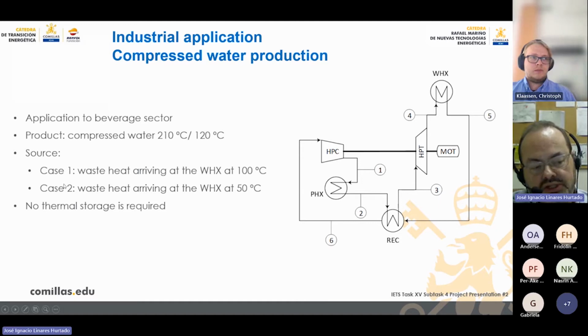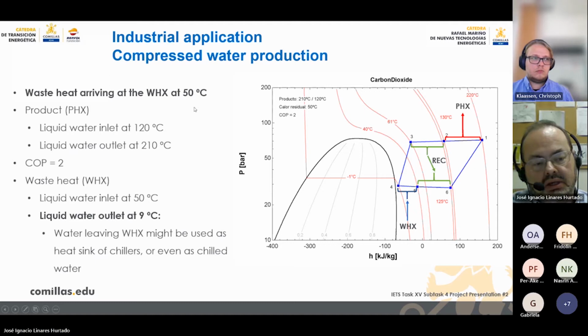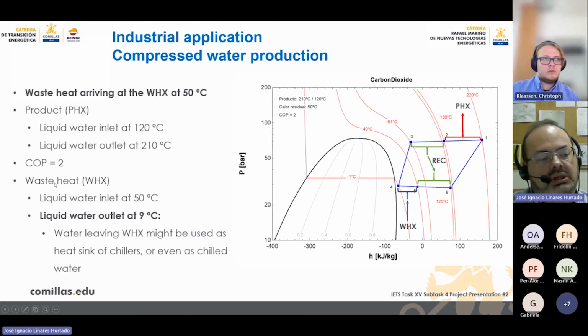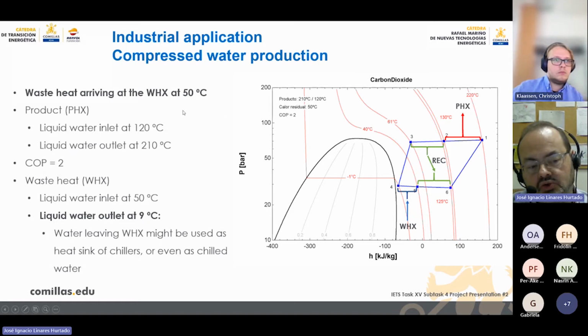We are going to study two cases for the source. One is waste heat arriving here at 100 Celsius degree, and another case at a lower value of 50 Celsius degree. Okay. With the lower temperature in the source, 50 Celsius degree, we obtain this position, this value. This is always the same. This is the requirement from the product. We obtain here a COP of 2. And very important, the liquid water outlet from 50 degree is cooled down to 9 Celsius degree.